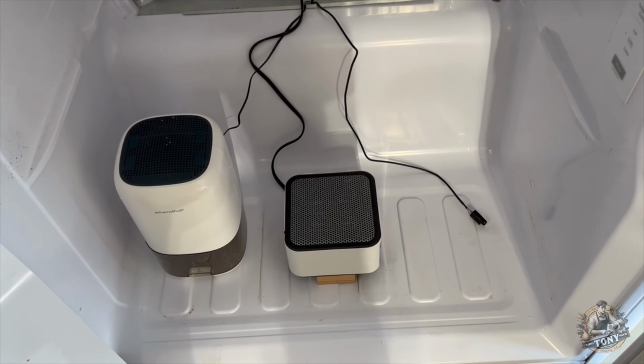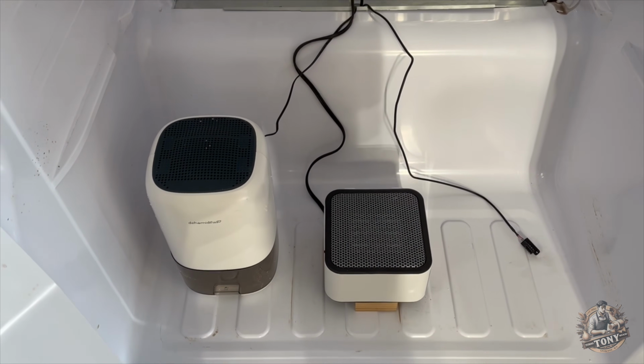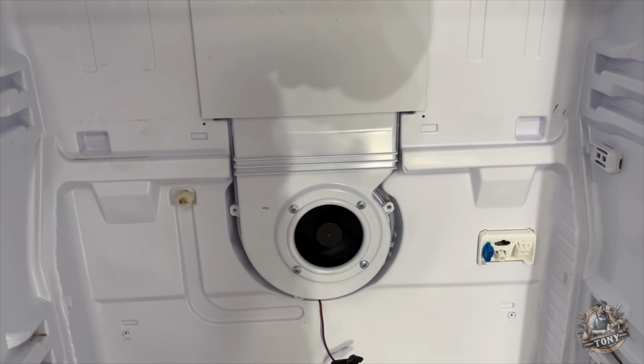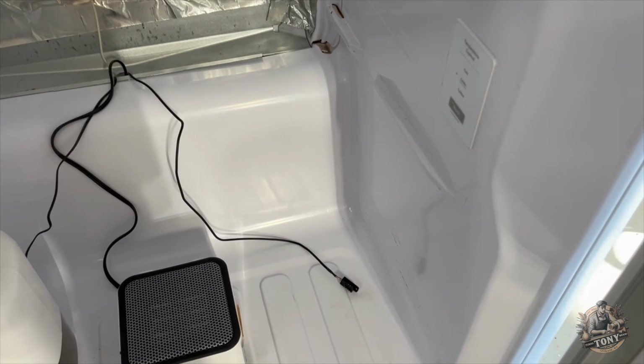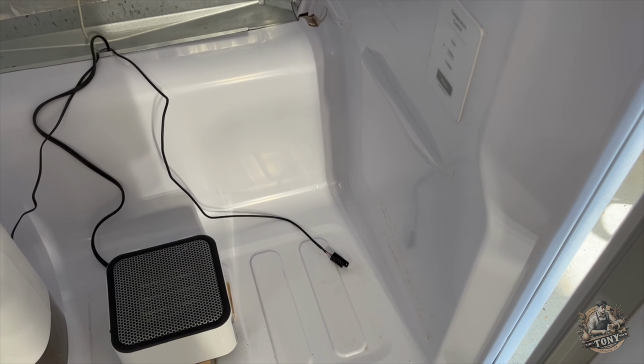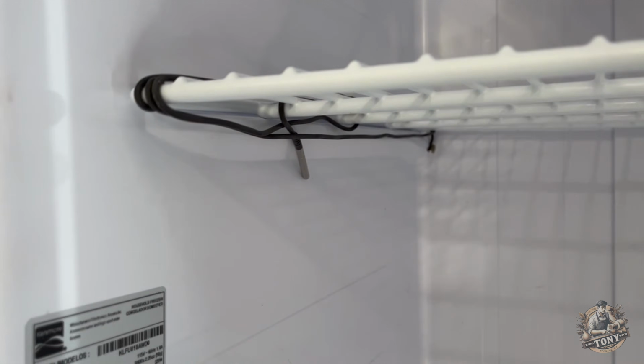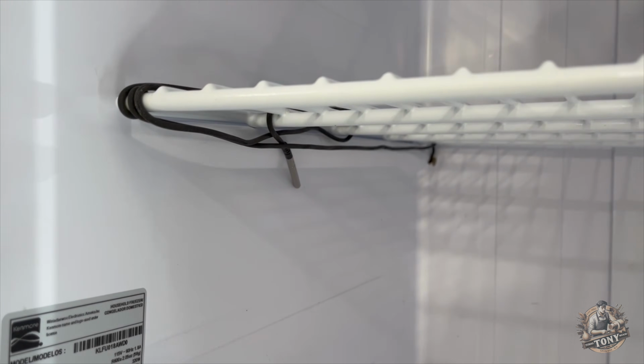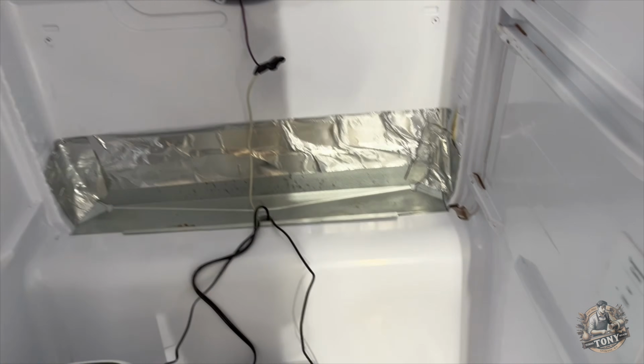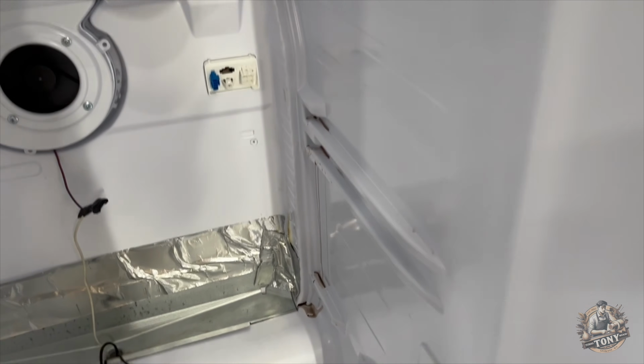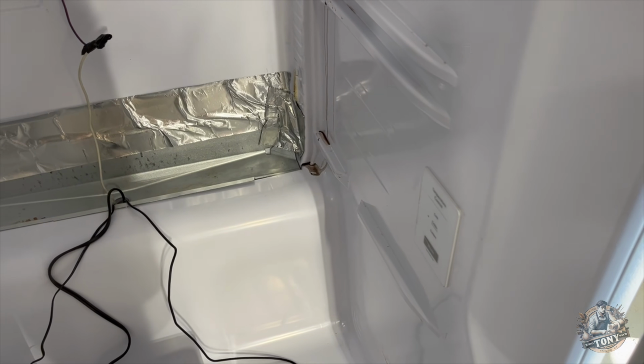And now we have our heater, our dehumidifier, our circulating fan, and our sensor for humidity down there, which we'll relocate after we put the cover back on, and our sensor for temperature up high. So heat rises, and the humidity should be relatively stable with the air moving, so we can leave the sensor near the bottom.